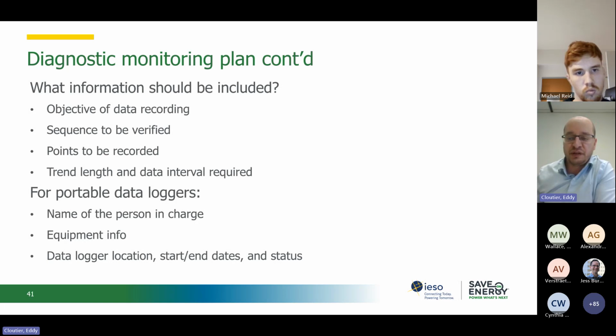For example, the objective could be to validate the percentage of outside air admitted into an air handling system by measuring mixing and outside air temperature in the air handling unit. Another example, we might want to check if we suspect a problem of poor adjustment of the PID parameters on heating or cooling valves, or we could also simply want to validate if the operating schedule of a system is respected. There's really a whole variety of information that we may want to validate in existing building commissioning.